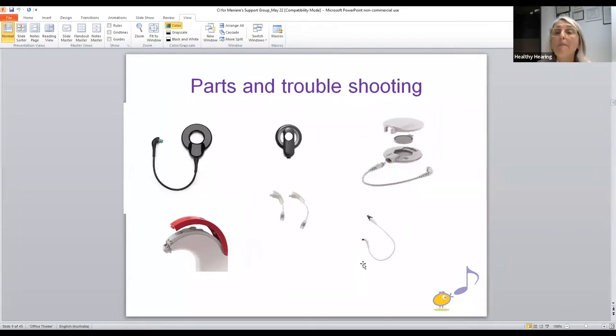So in terms of parts, things break with a speech processor, like any device. Usually things that can break are the coil and the cable. The cable breaks quite easily and needs to be replaced from time to time. Mostly manufacturers give you spare parts in your first kit, but after a while you need to pay for the replacement when it breaks.